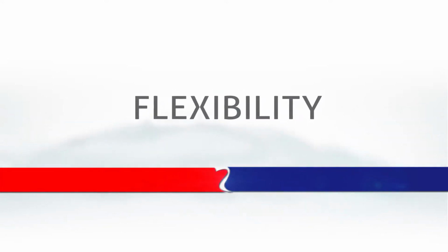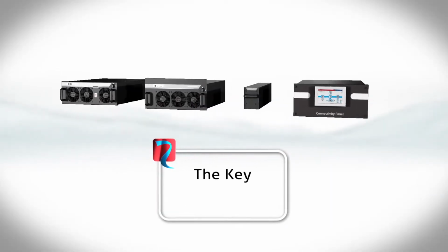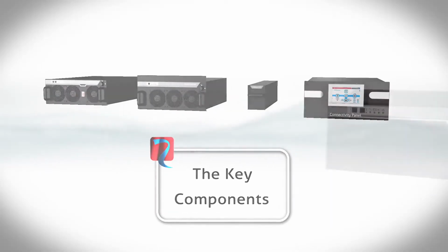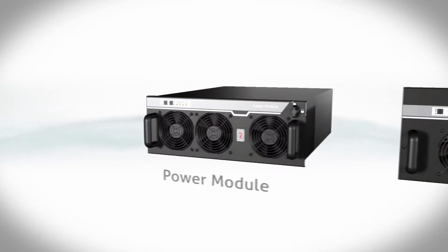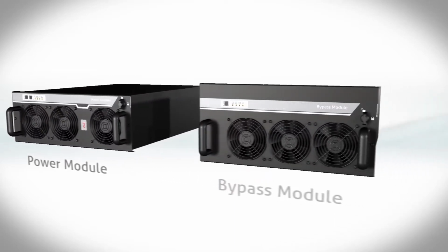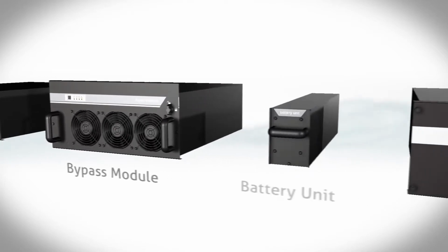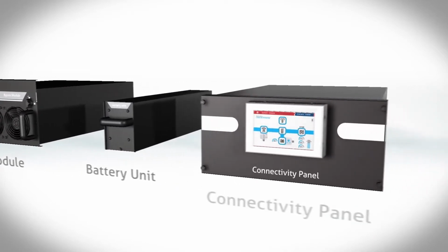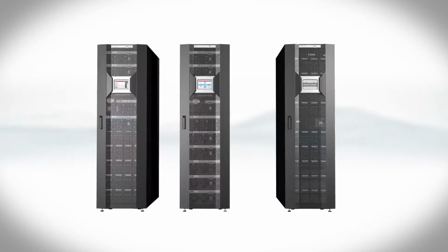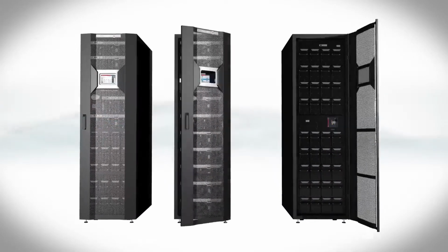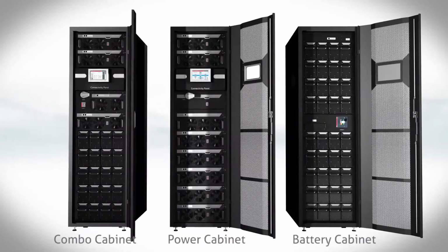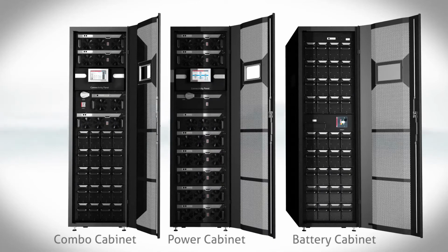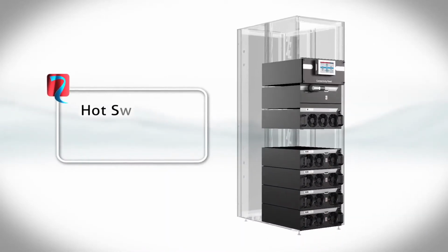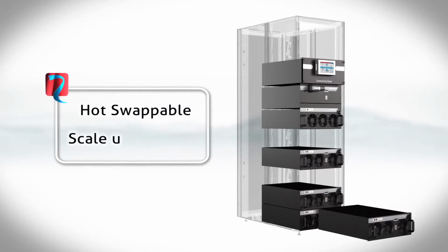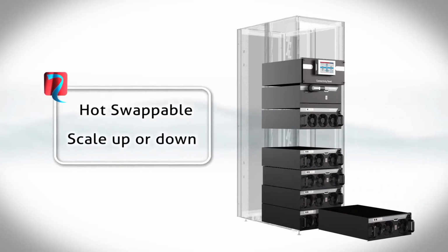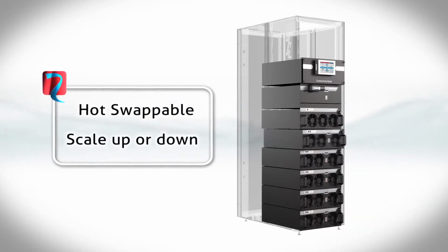Flexibility. To achieve maximum flexibility, we have separated the major parts of the UPS into its key component systems to ensure complete modularity: power module, bypass module, battery unit, and connectivity panel. A stylish range of cabinets house these modules to enable flexibility of installation and service. The main benefit of this feature was to ensure the modules were hot swappable, allowing painless scaling up or down or replacing as required, without the need to power down and affect the critical IT load.